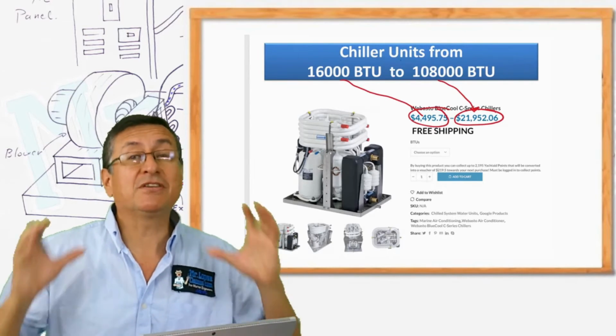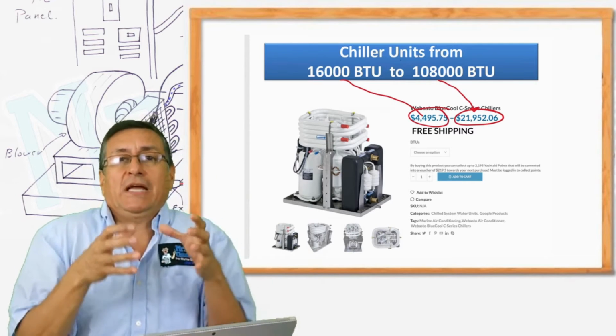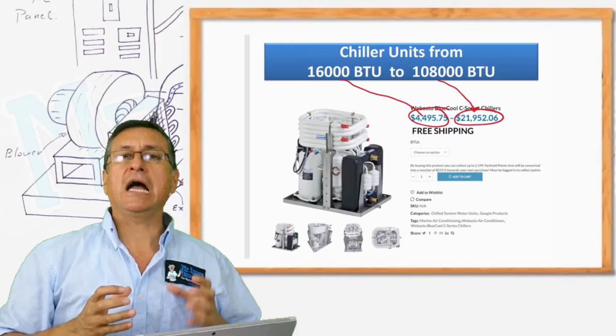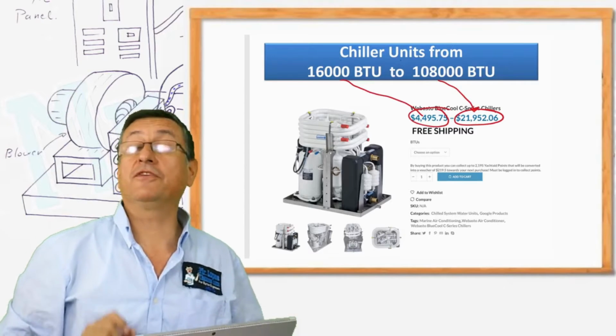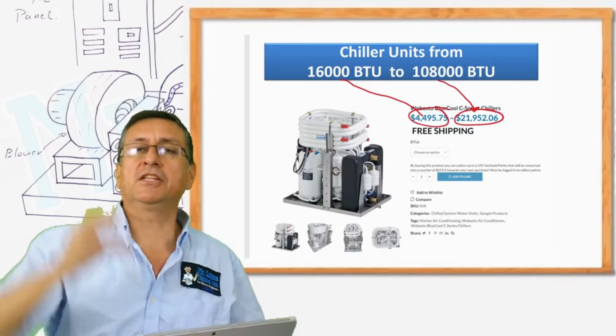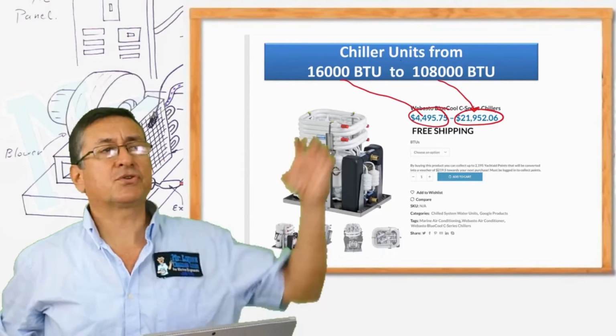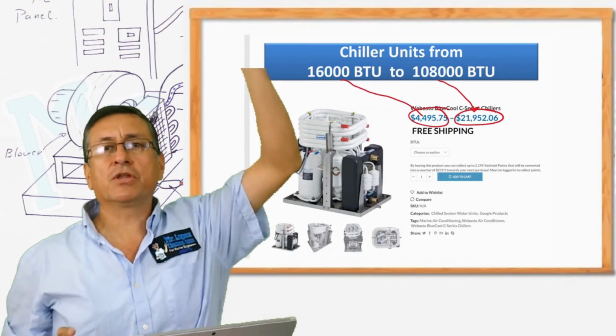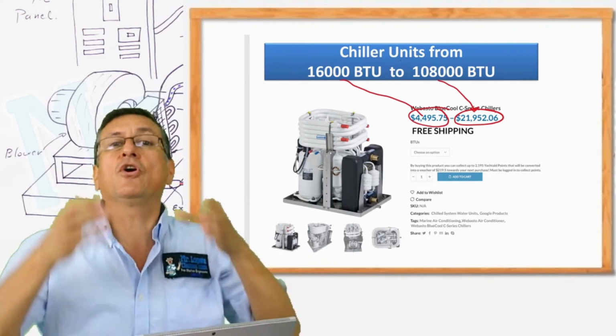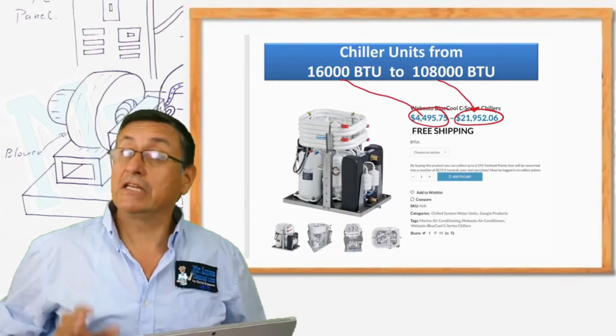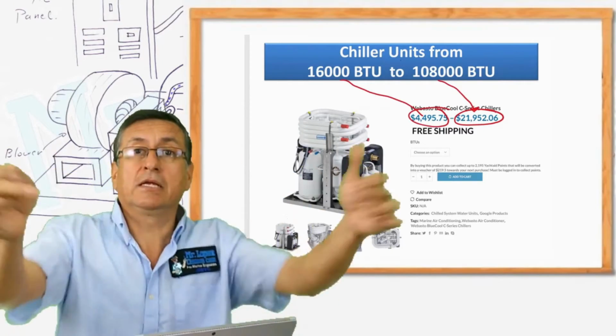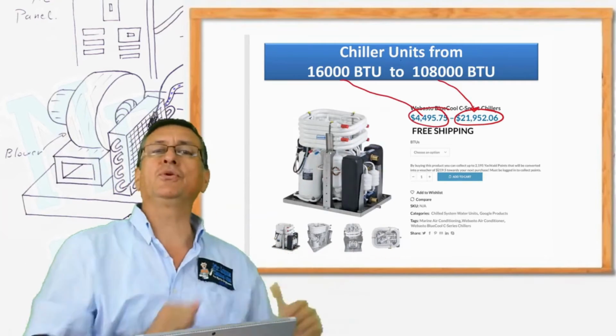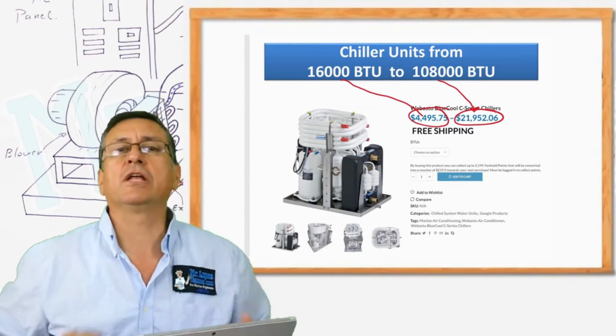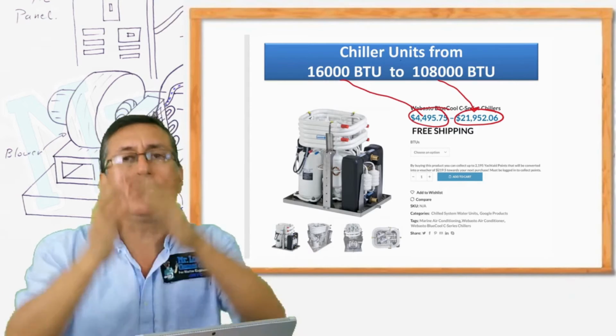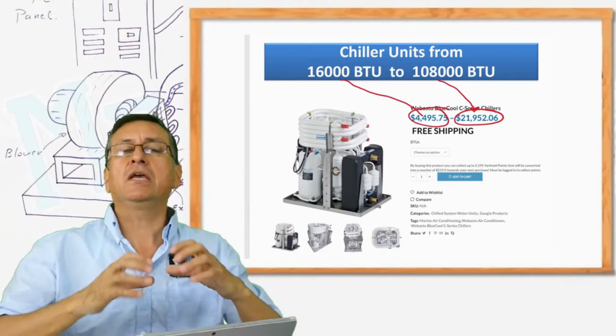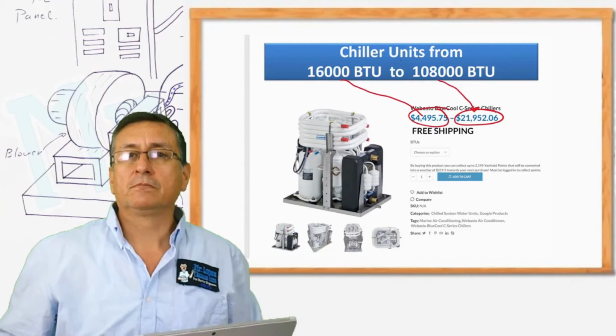Remember that if the boat is a big boat, I prefer a chiller unit located in the engine room, and I install air handlers in different areas of the boat: in the saloon, in the master room, another air handler in the guest room, in the fly bridge, another 4 or 5 air handlers with only one unit. Yes, you need to calculate the capacity per each area. Per each area, you add all of those BTUs, calculate the total capacity, and select the appropriate chiller. This is the most common design used today in the construction of boats, because it's efficient.